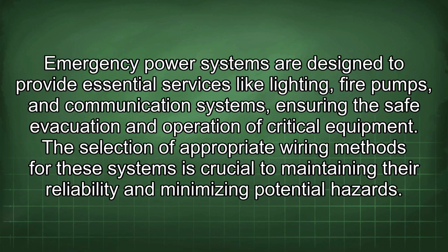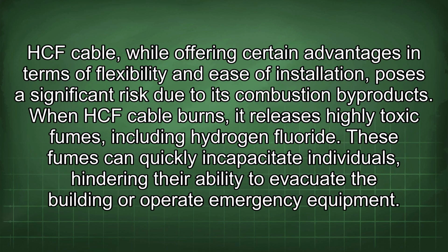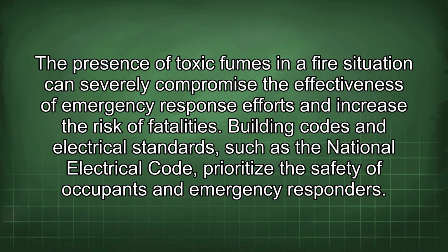The selection of appropriate wiring methods for these systems is crucial to maintaining their reliability and minimizing potential hazards. HCF cable, while offering certain advantages in terms of flexibility and ease of installation, poses a significant risk due to its combustion byproducts. When HCF cable burns, it releases highly toxic fumes, including hydrogen fluoride. These fumes can quickly incapacitate individuals, hindering their ability to evacuate the building or operate emergency equipment.